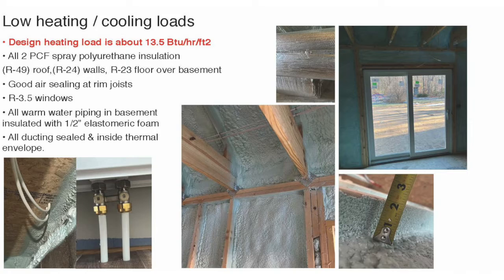And actually here you can see a couple of the half-inch tubes. These just go up to a panel rad. So there's just 2 holes, 3/4-inch size holes, 2 inches on center. The 2 pieces of tubing go up. They go into a dual isolation valve. There's a ball valve here and a ball valve here. If you ever have to take that panel off or isolate it, you just take a screwdriver, close those 2 ball valves off, and there's unions, half unions here, and you can break those unions and you could lift the panel right off. Here's the spray foam again, 7 inches, which is R49 up here.